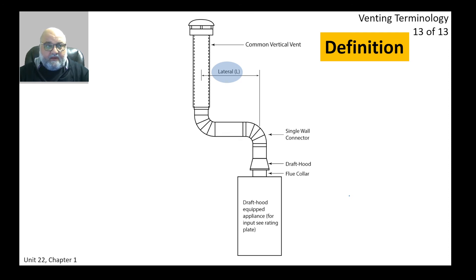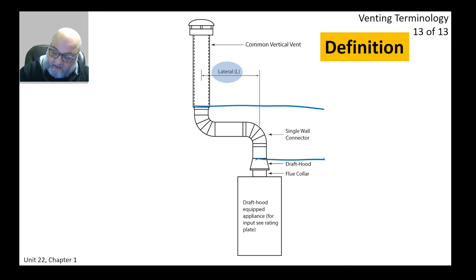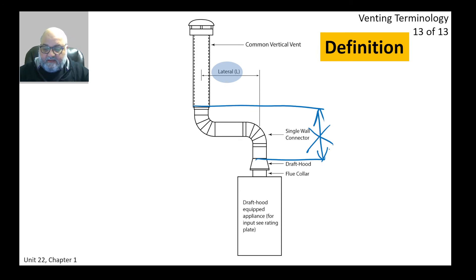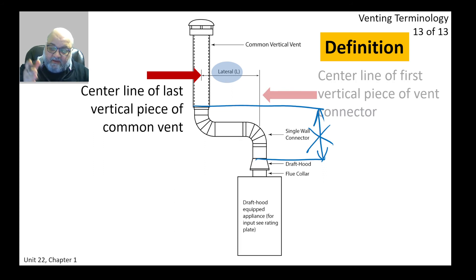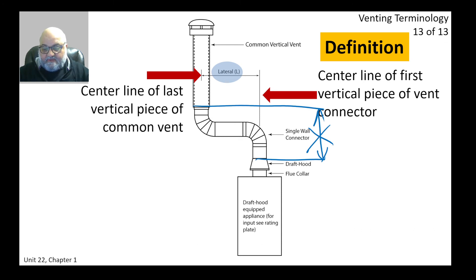For a single appliance there is no rise — we don't discuss rise for a single appliance. Instead, we talk about the lateral distance: the distance between the centerline of the last vertical piece of common vent and the centerline of the first vertical piece of vent connector. That lateral distance is very important for single-appliance applications.